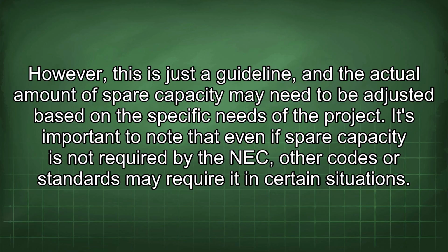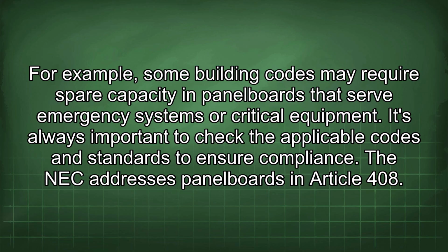It's important to note that even if spare capacity is not required by the NEC, other codes or standards may require it in certain situations. For example, some building codes may require spare capacity in panel boards that serve emergency systems or critical equipment. It's always important to check the applicable codes and standards to ensure compliance.